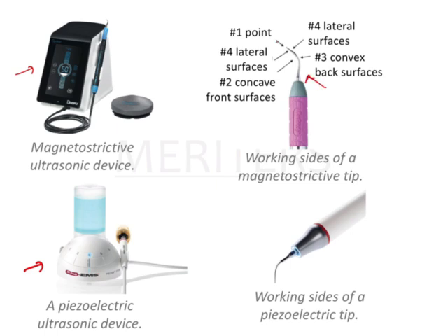This is the magnetostrictive tip. You can see the point of the tip — that is the first working surface. Then there are the lateral surfaces — the second lateral surface. Then the back surface, which is the third working surface. And if you see this concavity — the front surface — that is your concave surface. So there are: lateral side, point, convex surface, and concave surface — these are the four working sides of the magnetostrictive tip. For the piezoelectric tip, there are the lateral areas and the tip, giving two working sides.